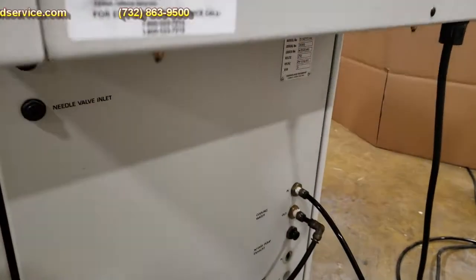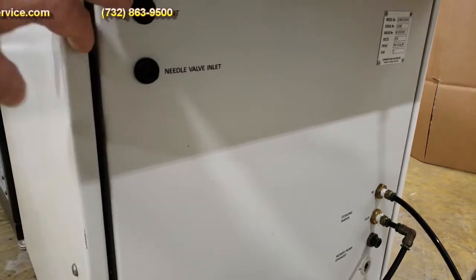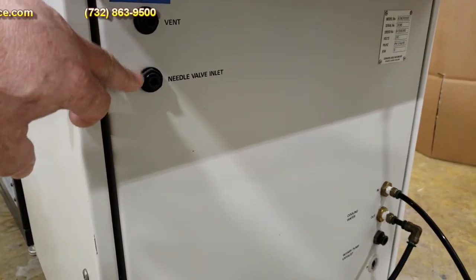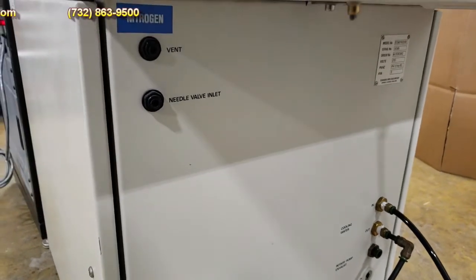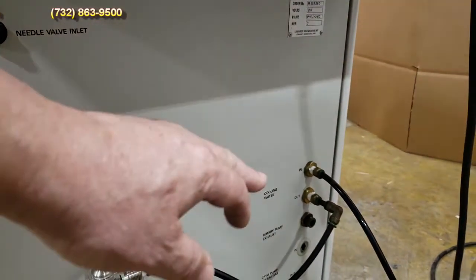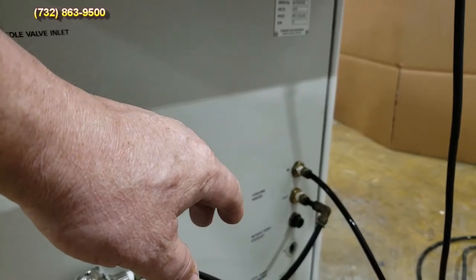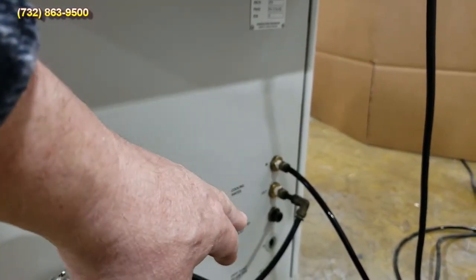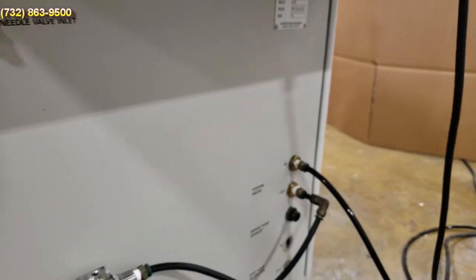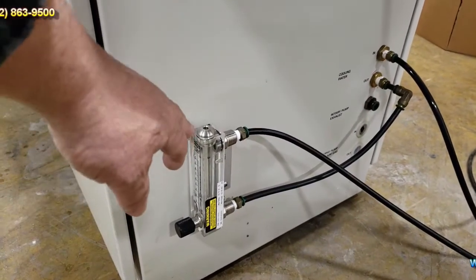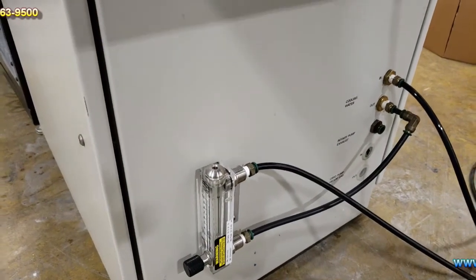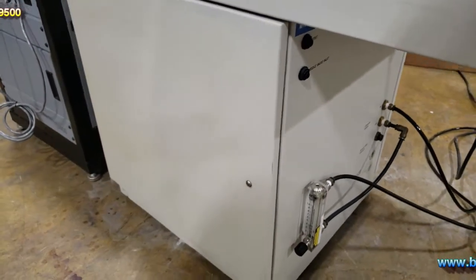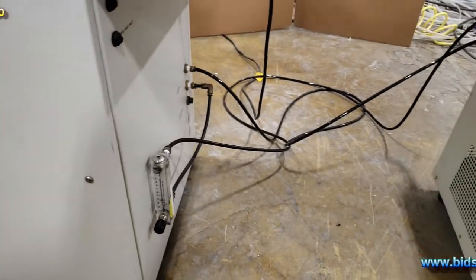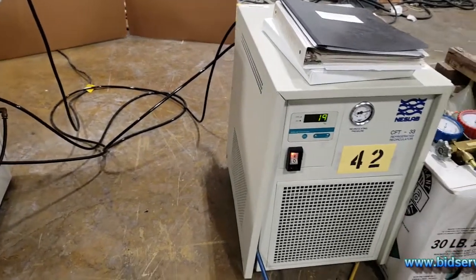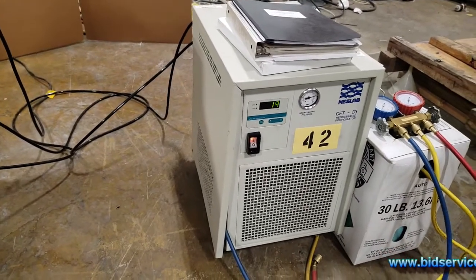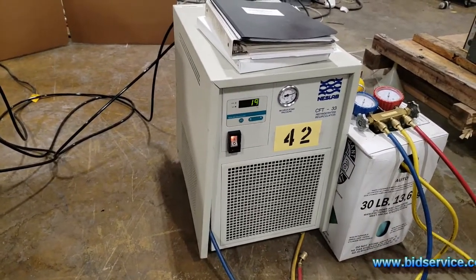Underneath here, you basically have your vent and your needle valve inlet for your gas, pressure gas if you want, or process gas. You have down here your cooling water lines. You have your rotary pump exhaust below that. And over here, there's a flow meter on here to monitor the water. This is water cooled, so you will need to have a chiller. This chiller here does not go with it, but it is on sale on our site. As you can see, it's being repaired at the moment.